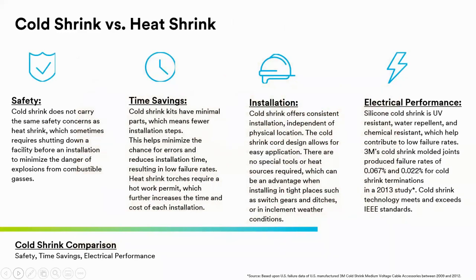So as you can see in that video, the cold shrink tubing did continue to shrink down to its smallest size and continued to create that inward pressure on the toothpaste tube. So just to summarize, cold shrink eliminates safety concerns associated with heat and open flames. There are no permits involved when using cold shrink. You don't need a heat permit of any sort. It's much quicker and easier to install than heat shrink, and you're avoiding installer error, not having to rely upon the installer's experience with heat shrink versus cold shrink. And the overall electrical performance is much better, and 3M's cold shrink terminations and splices have extremely low failure rates over time.